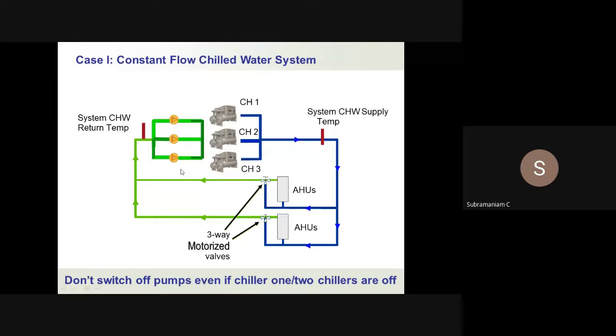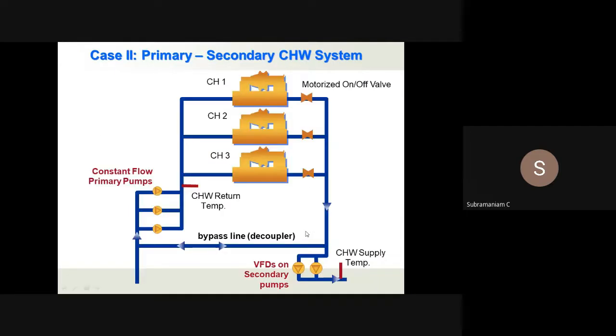That is important. So that control is a different method. You will have to reset the chilled water leaving temperature of the operating chiller to get my mixed temperature as per design, so that I will not compromise on chilled water flow requirement at the last AHU. This has been the problem before the primary secondary came. Now when we have a primary secondary system, those problems are all sorted out, because you are decoupling the production of chilled water and the demand of chilled water.